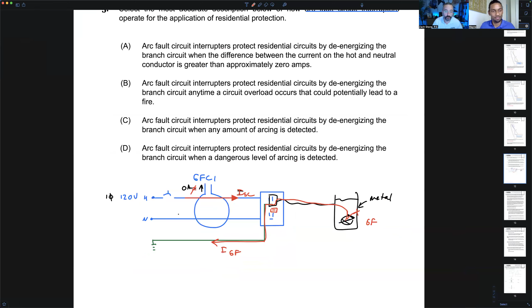Does that make sense on how a GFCI works? Yes, it does. The reason why this is helpful is circuit breakers are huge for residential safety, right? A circuit breaker should trip on overload if this blender is heating up, or my vacuum trips one of our circuits all the time. If we're really vacuuming the carpet, the motor's getting hot, the motor's drawing more amps. As that overload increases, that should pop the breaker, or technically a ground fault is still a short circuit. It should also trip the breaker, right?